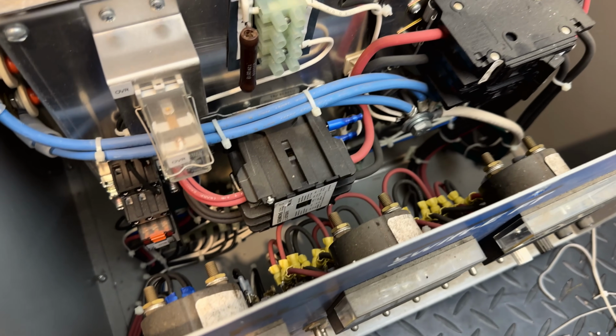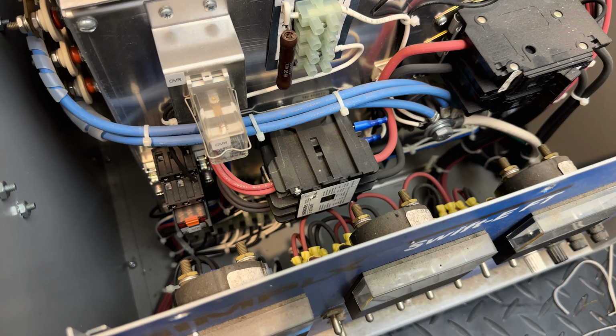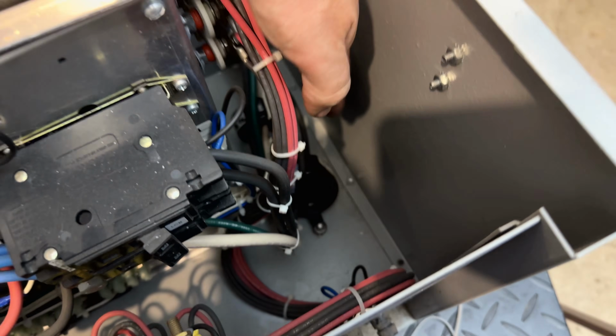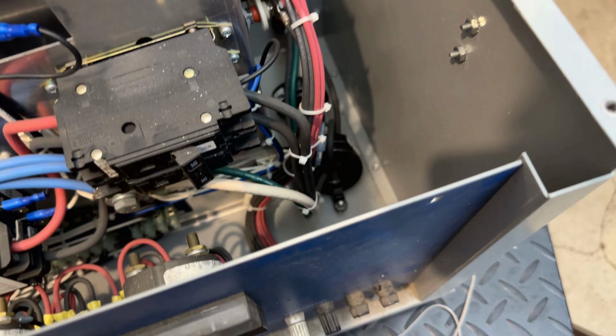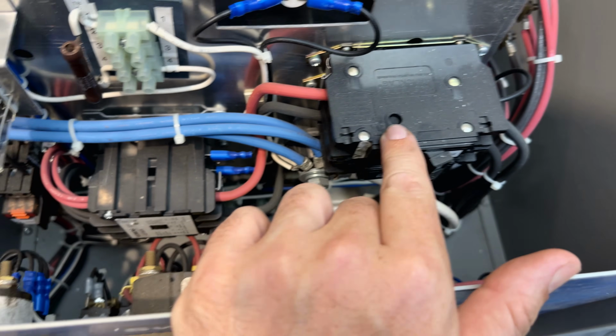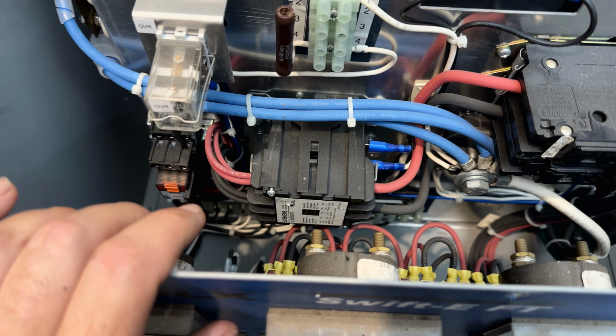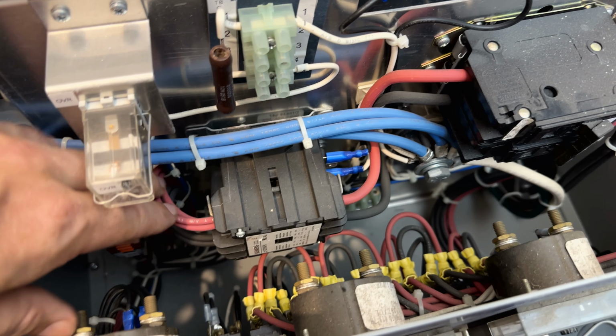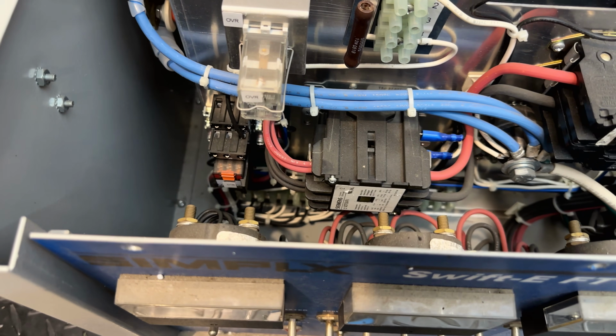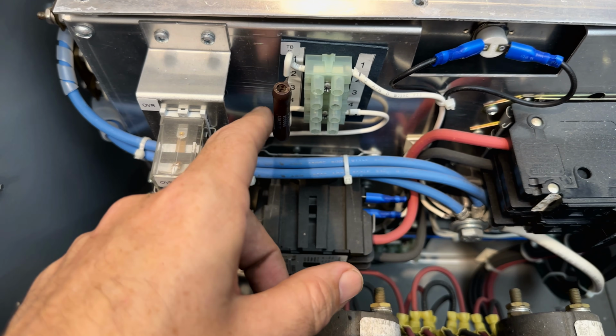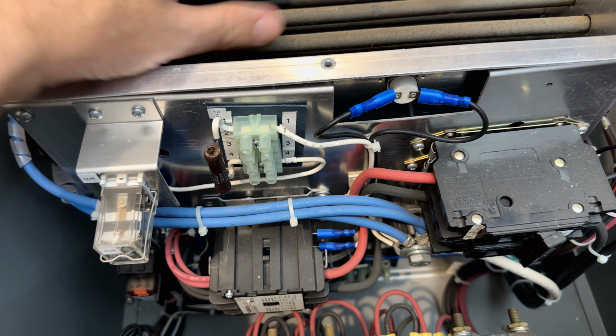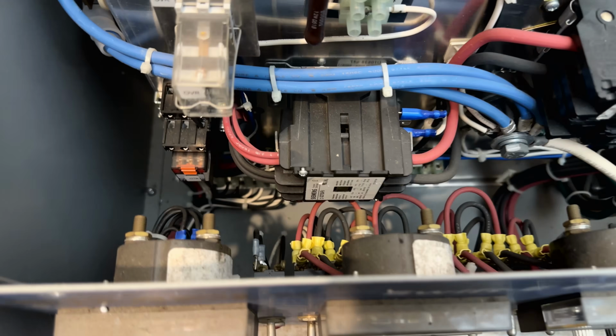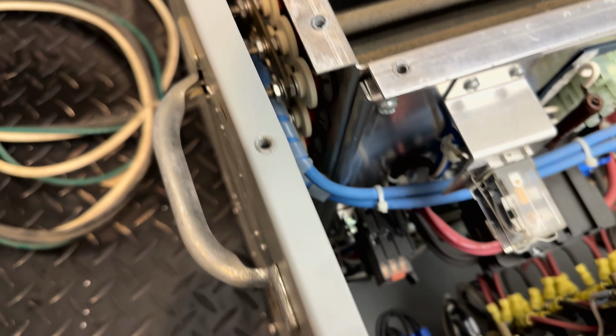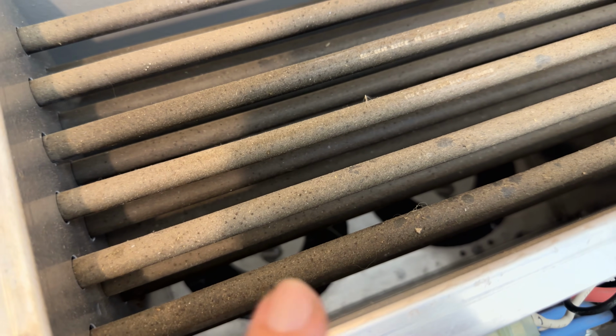I've got to say, I was not expecting such organized chaos. There's a lot of stuff going on in here. Starting on the right, we have these two large current transformers on the wires coming in, and those feed up to a 50 amp breaker, which then goes over to this device here, which I'm not quite sure what it is. I don't think it's a breaker, but it does look to be breaking out those large cables into several smaller gauge cables, so that might be its purpose. We've got a couple of relays, and it looks like a temperature sensor right here, and possibly another right there, maybe one for monitoring the heating elements and another just to monitor the general temperature in here. Otherwise, there's not a lot going on. We have a bunch of wires going over to the heating elements, two fans in the bottom, and a bunch of wiring for the switches and gauges.